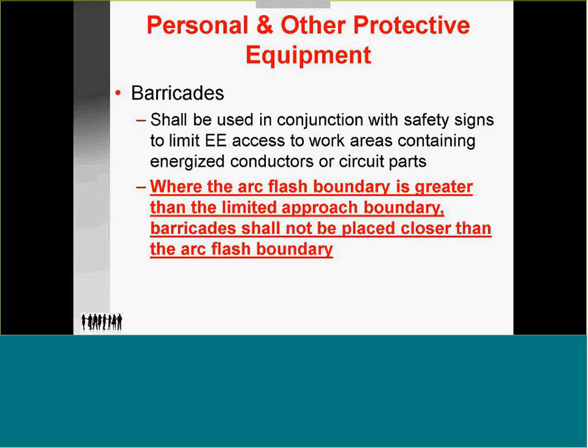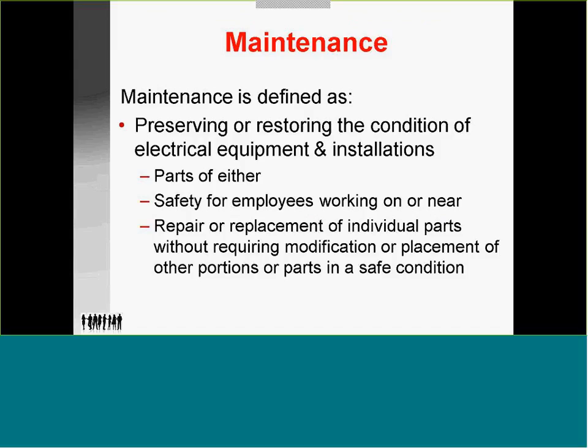This is where the limited approach boundary is mandatory to be put up if you open a panel that has live parts. Now, if you have isolated a 480 and has control voltage of 120 single phase inside the panel that is not isolated, that is considered live work, energized work, whatever you want to call it.